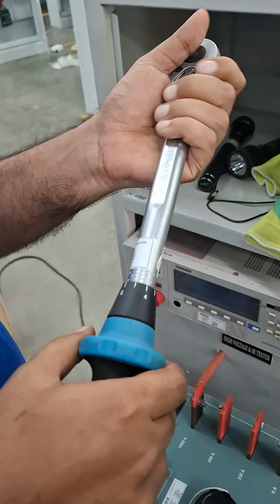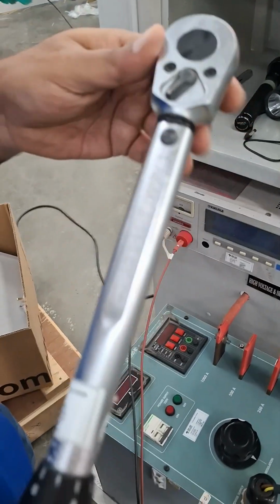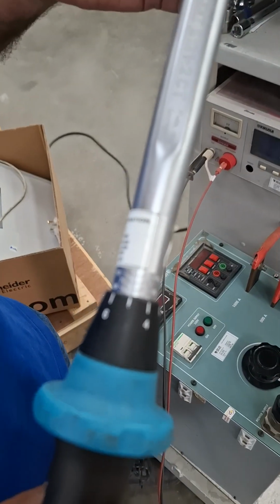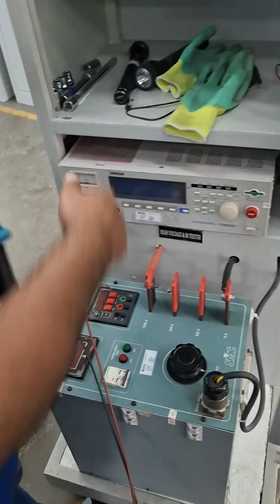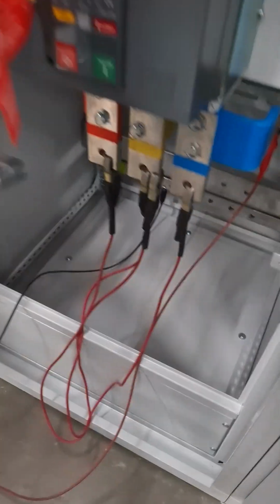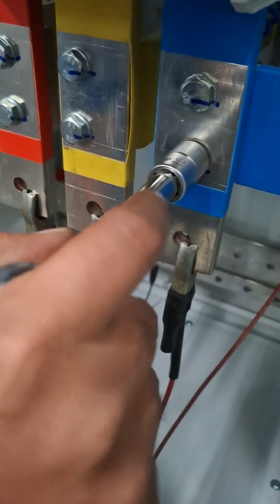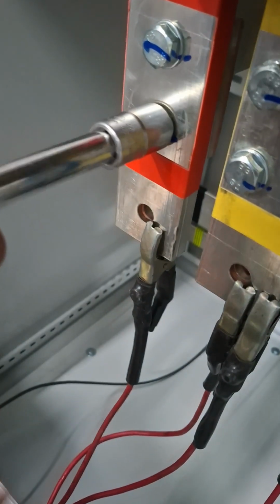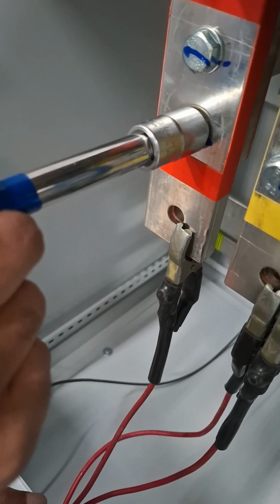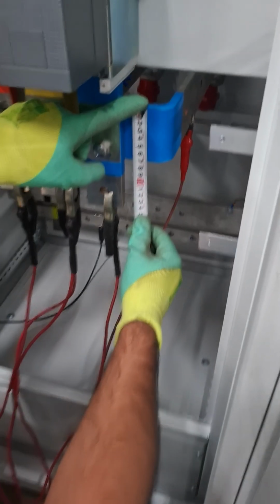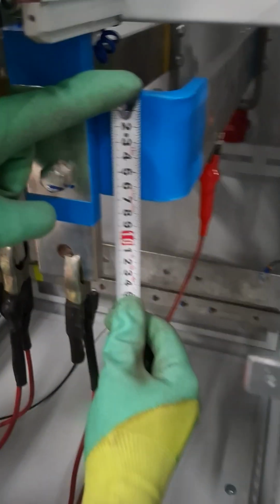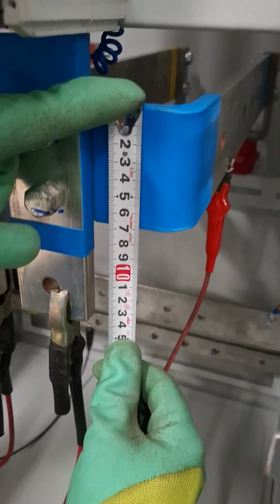Now we check the torque. Okay. Set the value at 45. Okay. This is the 10 mm bolt. Now check the torque. Okay. All bolts are marked. Check. Okay. So now he is checking the bus bar size. This is the 70 by 10. Okay.